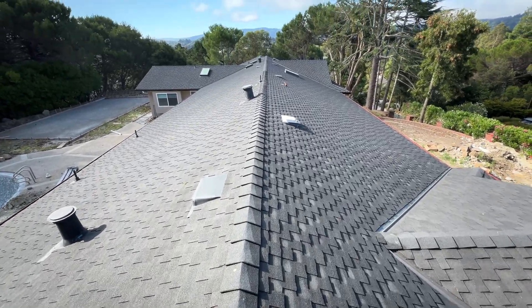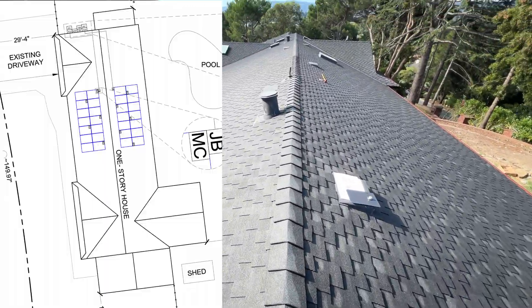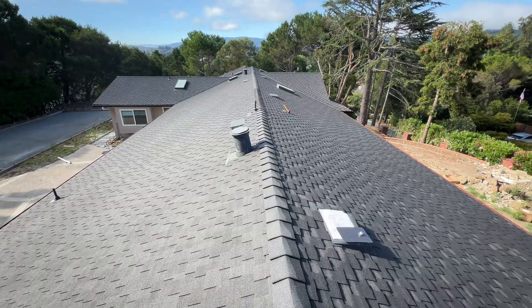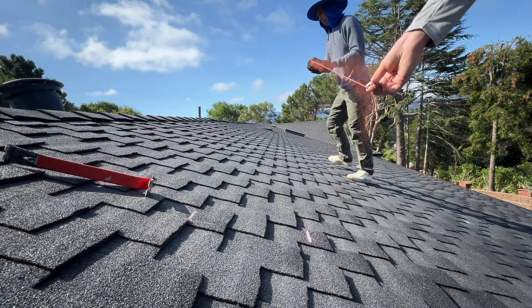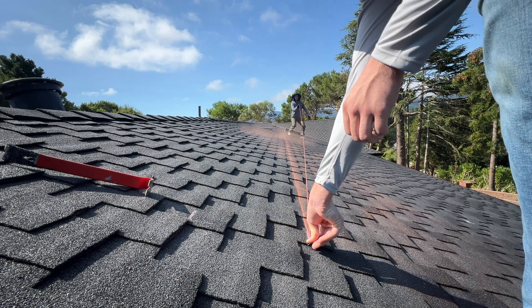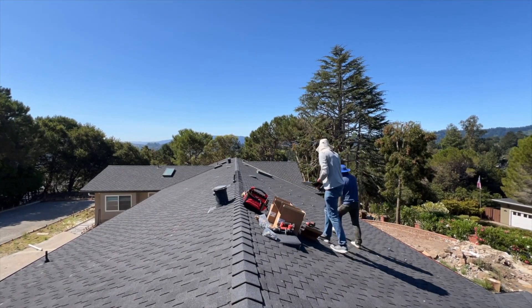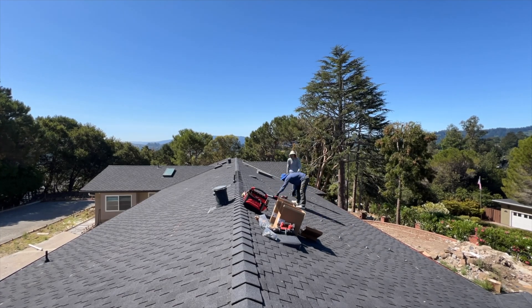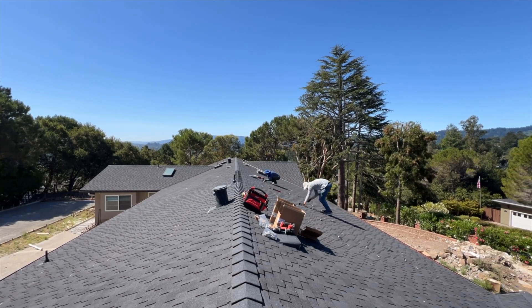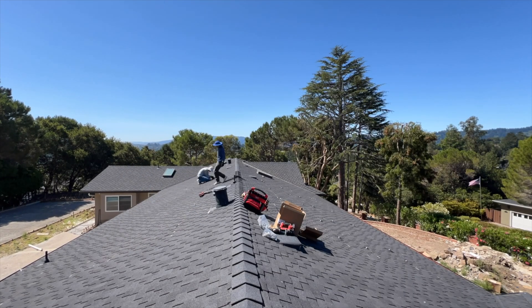The roof material is composite shingles. We're going to have 14 panels on the left side of the roof and 14 panels on the right side. We're going to do a chalk line to install all IronRidge L-feet in an ideal line. For this project we're using IronRidge XR100 rails, which means we can do 72-inch spacing between mounts, and we're going to use 48 IronRidge FlashFoot 2 mounts.